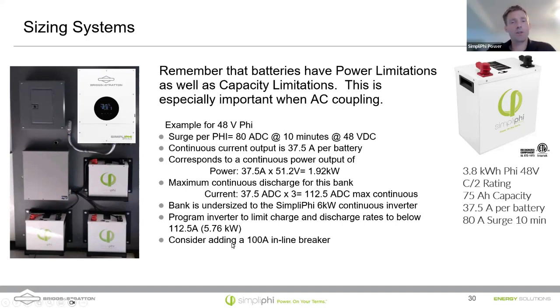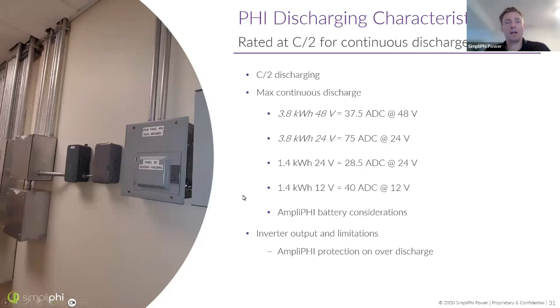You could also consider adding a 100 amp inline breaker. Now, why am I saying 100 amps even though you have 112 amp discharge? Well, breakers typically don't trip exactly at their full load. It takes longer for that to happen.